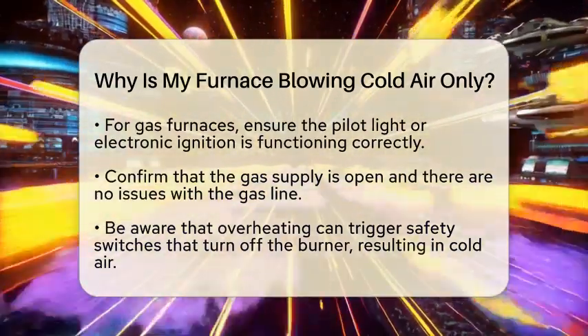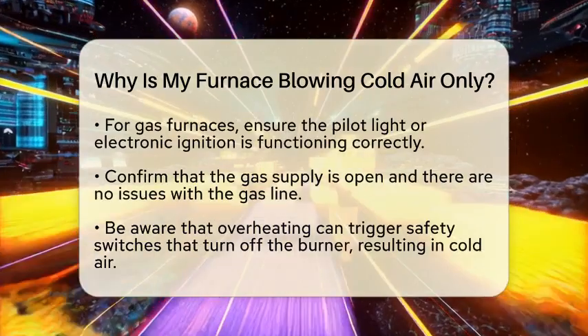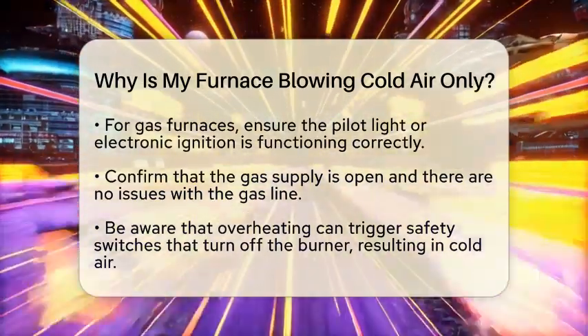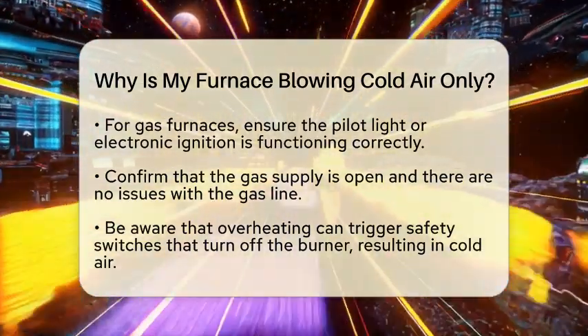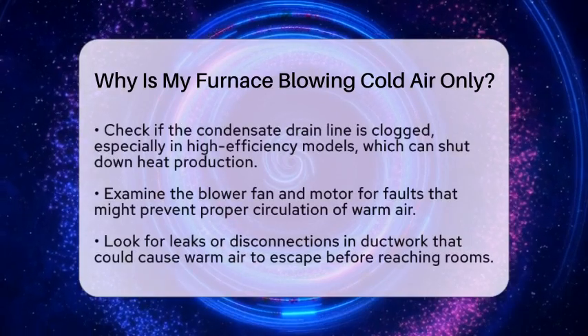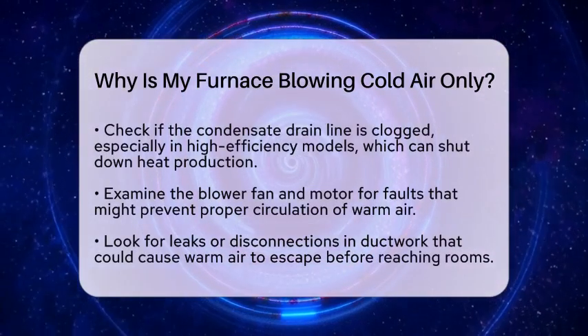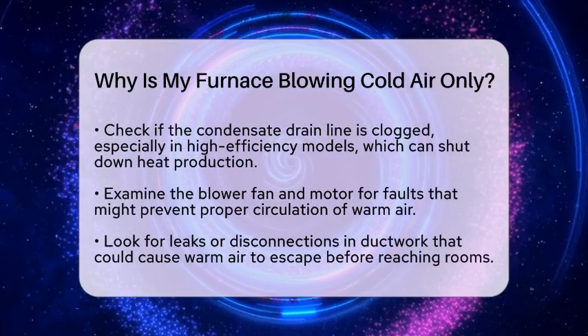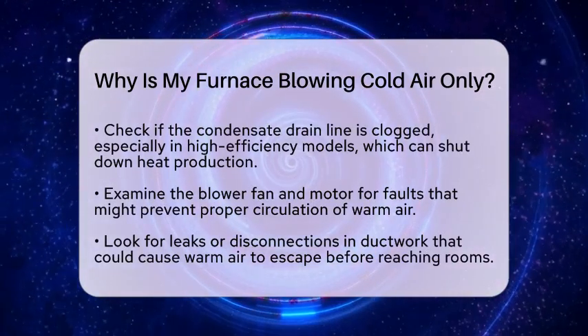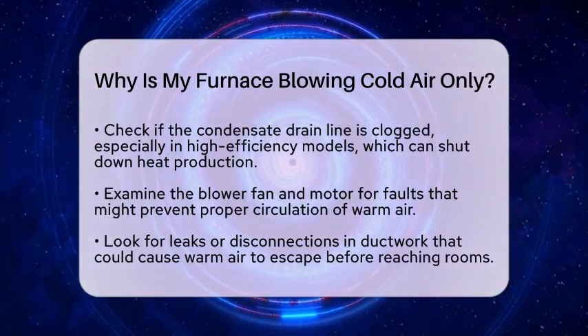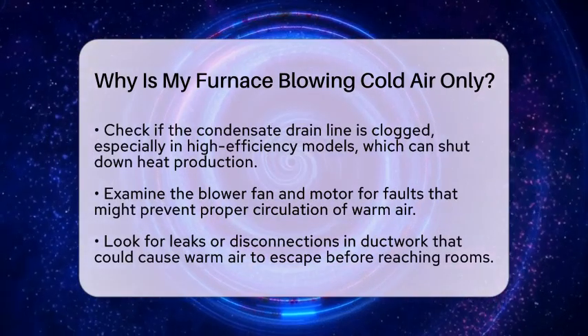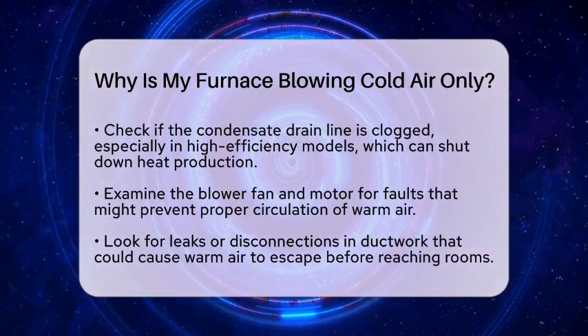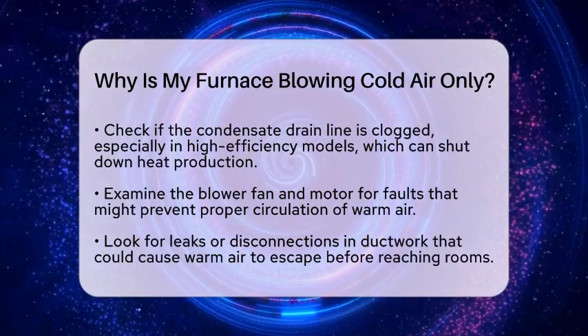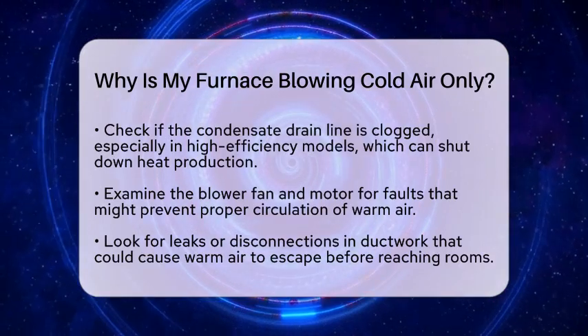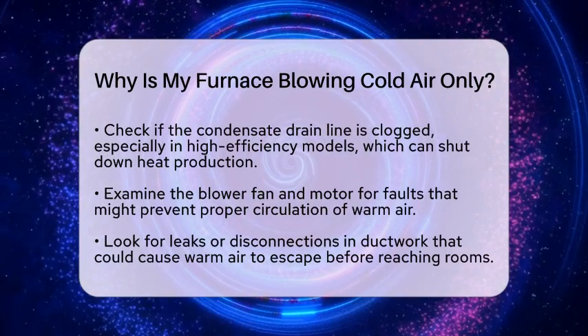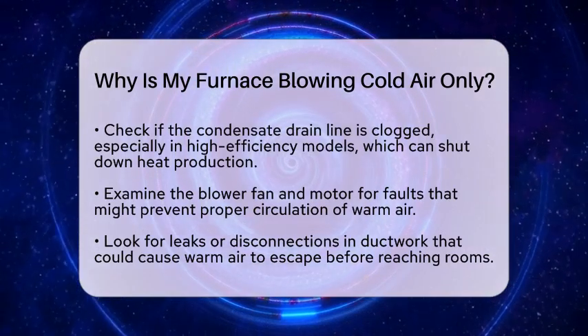Overheating inside the furnace can also cause safety features to shut off the burner. Dirt buildup, mechanical failures, or an aging system can cause the high-limit switch to activate. When this happens, the burner turns off to prevent damage, but the blower might still run, pushing cold air through your vents. High-efficiency furnaces have a condensate drain line that removes water produced during operation. If this line gets clogged, it can trigger a safety shutdown, stopping heat from being generated.